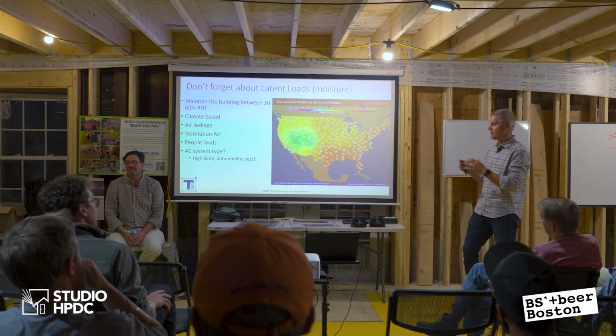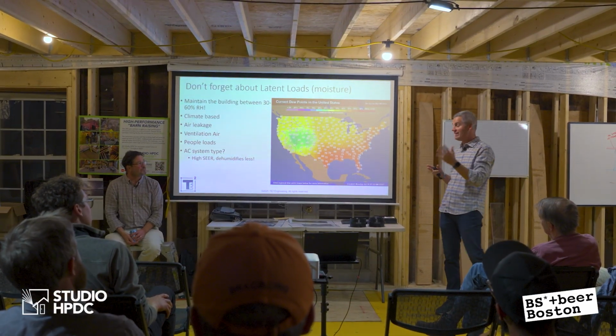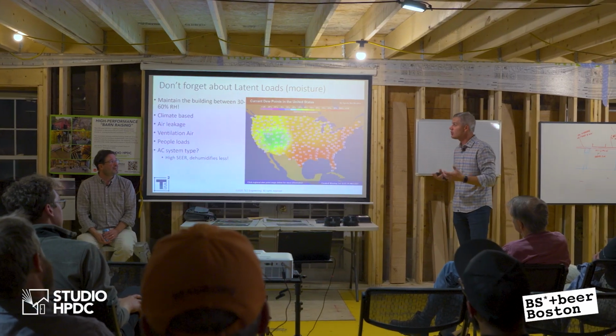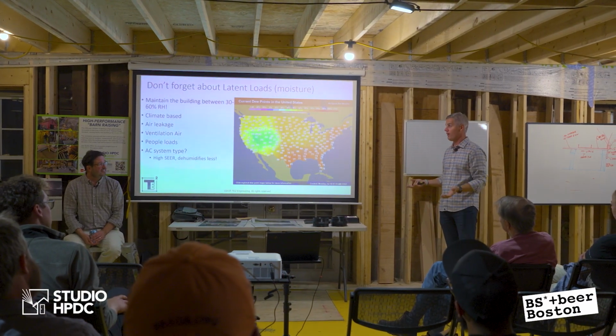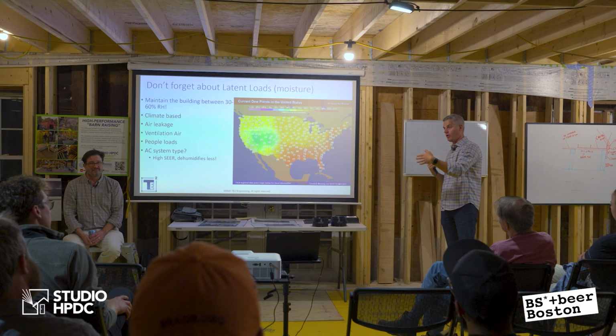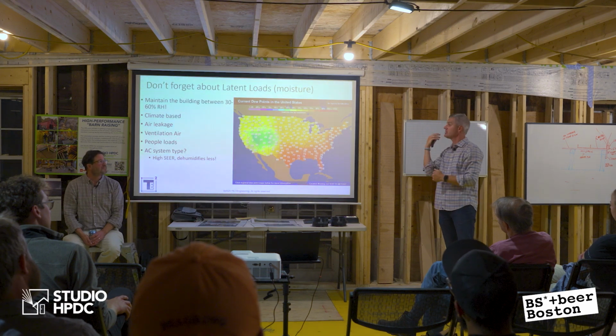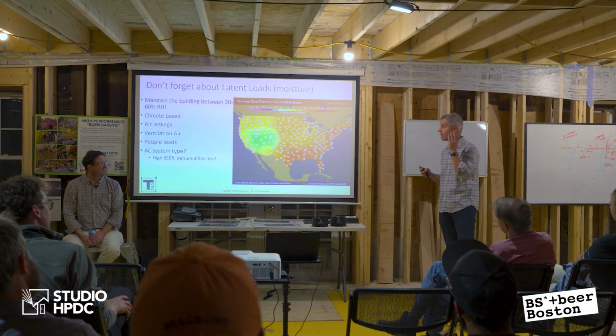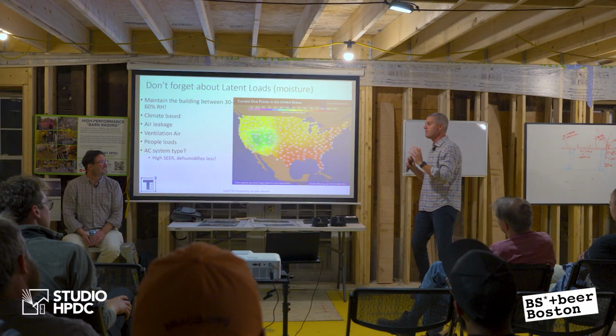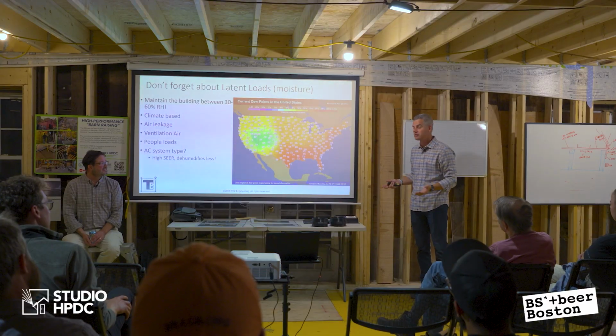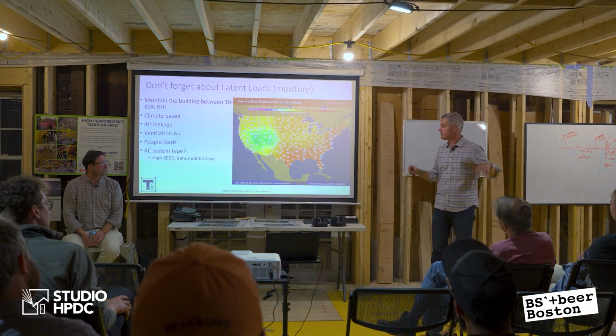But if I can play with the sensible heat ratios, which I can do with chilled water, that's what they do in commercial systems all day. They've been doing it for 100 years. If I can change the water temperature, the water flow rate and my air handler flow rate... everyone's always been fixated that air handlers have to be designed for 400 CFM a ton or 350 CFM a ton. That's with a traditional refrigerant-based system. With chilled water, I could run 200 CFM a ton, I could run 150 CFM a ton.